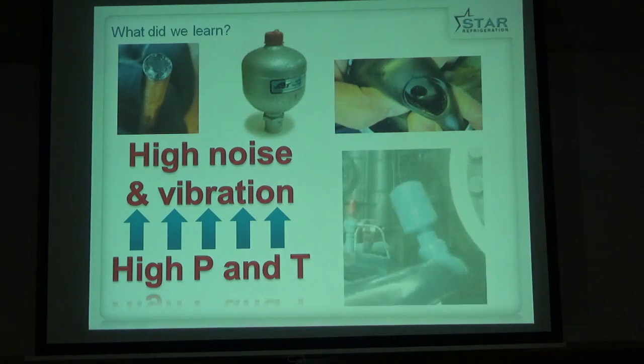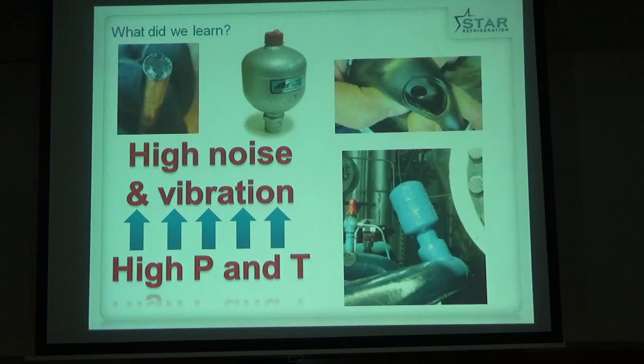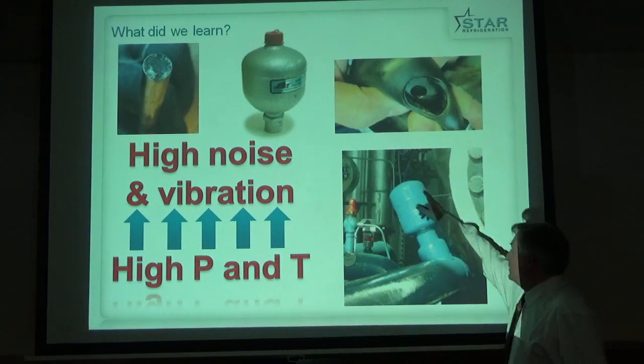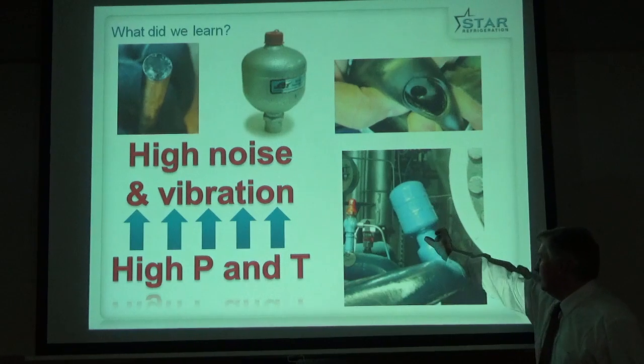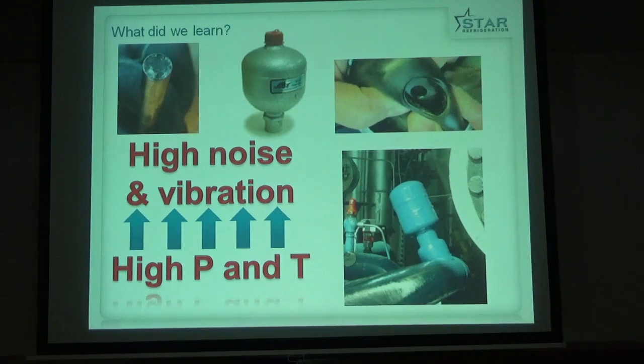We then fitted what's called a Helmholtz resonator. This is really neat. This is like the F holes in a violin, which cause the sound to resonate. This little pot is sized to be just the right volume versus the diameter of the neck that it responds at a specific frequency, and it creates a negative sound wave that cancels out the positive sound wave that's coming along the pipe. Before we did this, we had a noise level coming off the compressor which was way higher than it should have been.